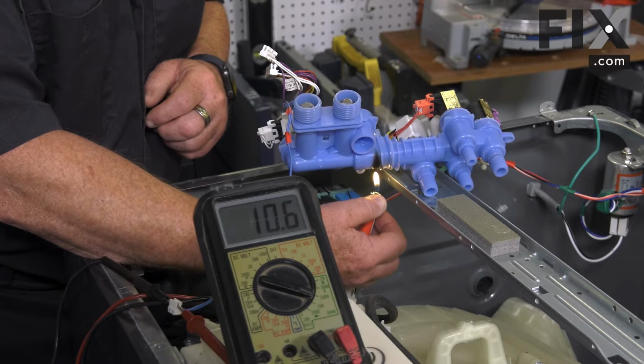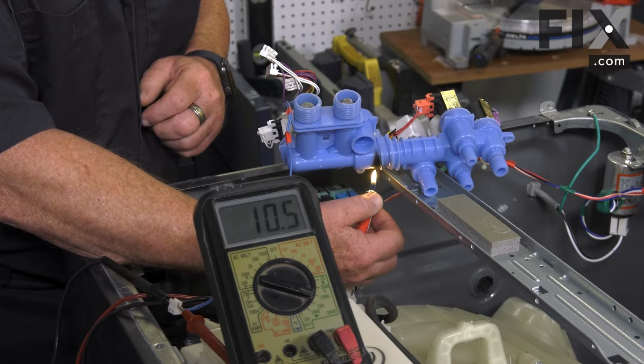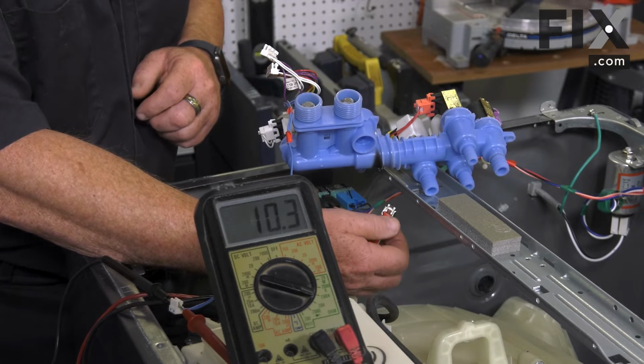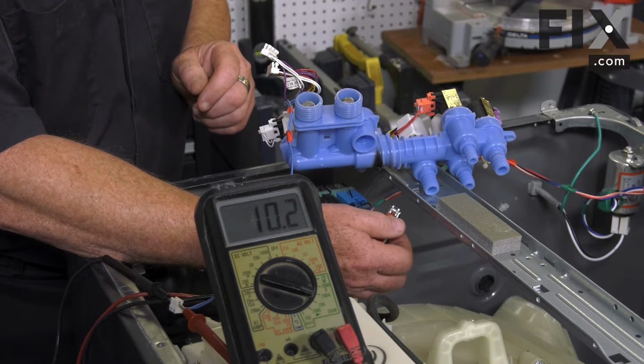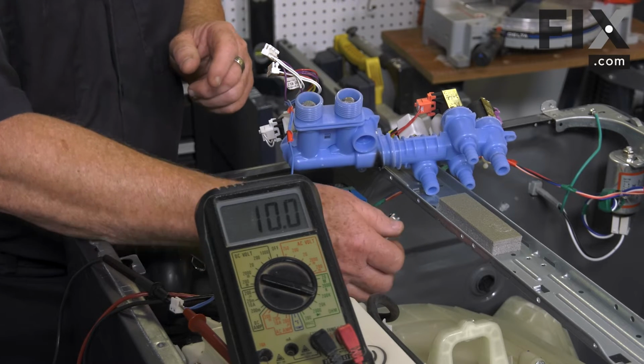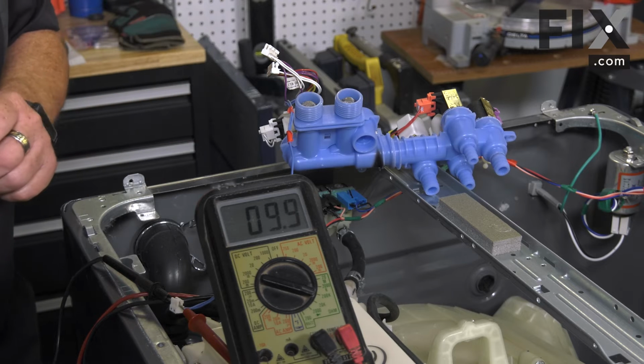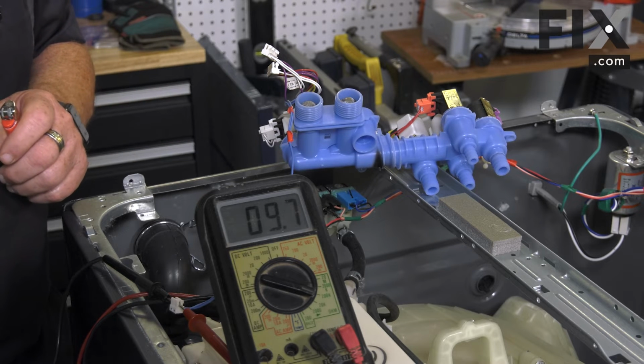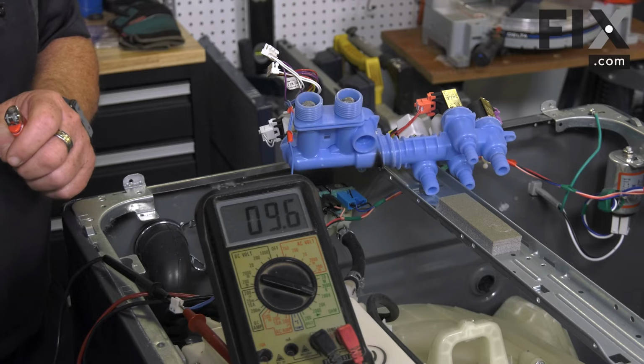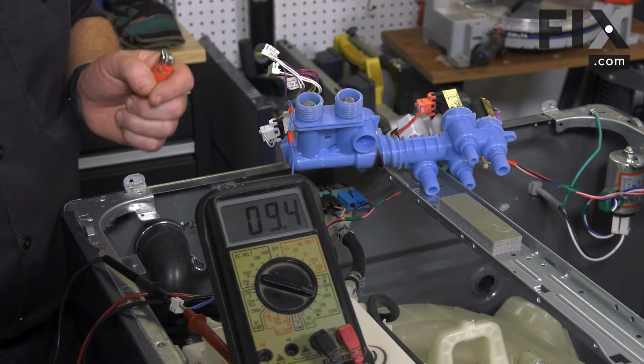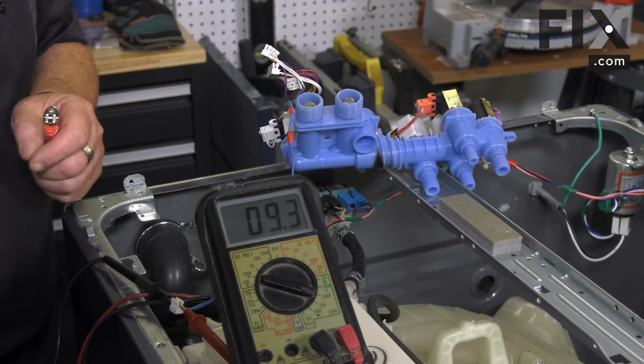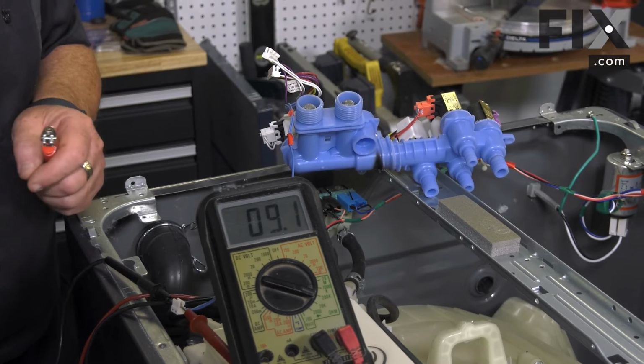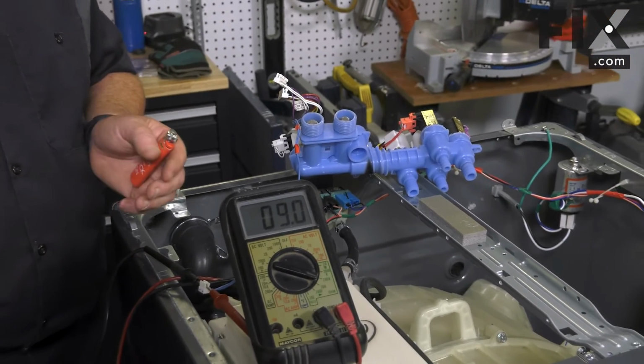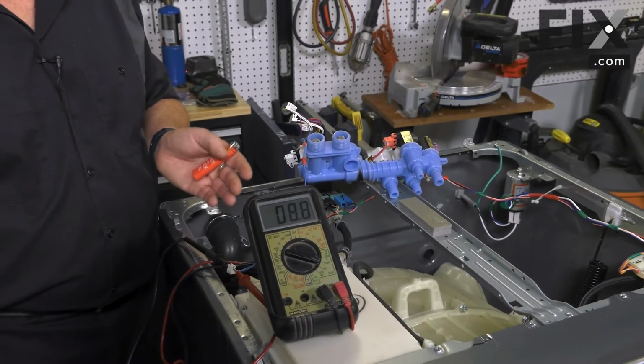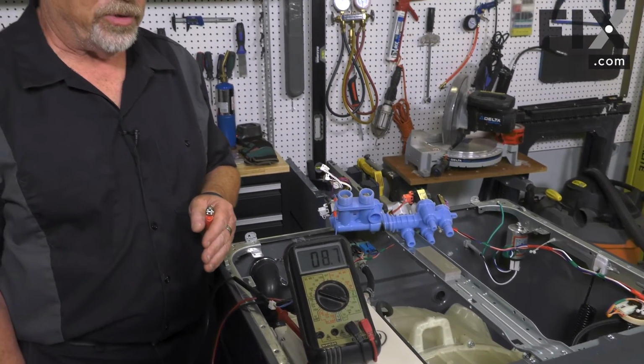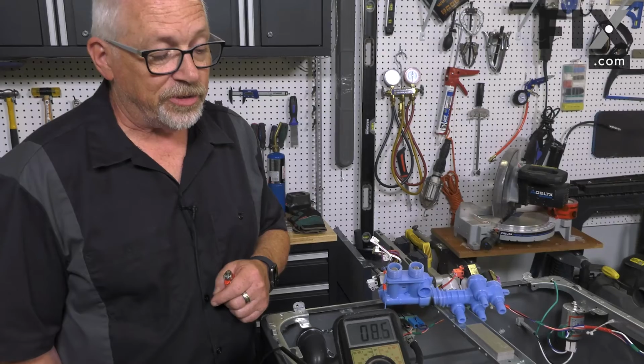So you can see that's starting to change as the heat's being applied. So if that was hot water starting to go through that valve, you would see that starting to change. And as I remove the heat, you'll see it go back into its original temperature setting. So that change in the thermistor, that change in the resistance, tells the control board what's happening as far as the water temperature goes. So that's how it's going to decide whether it needs to add more hot water or reduce the amount of hot water that's going into, say, a warm temperature selection.